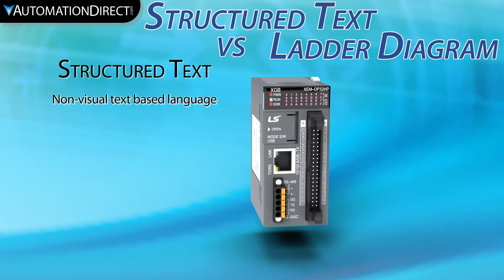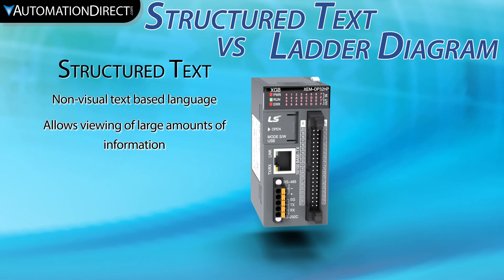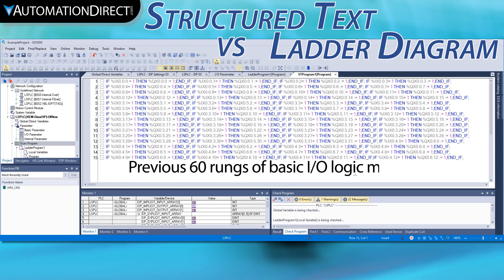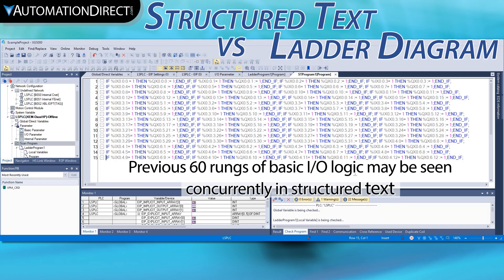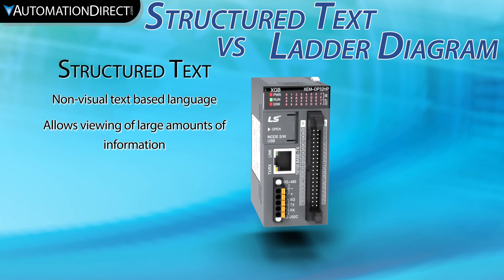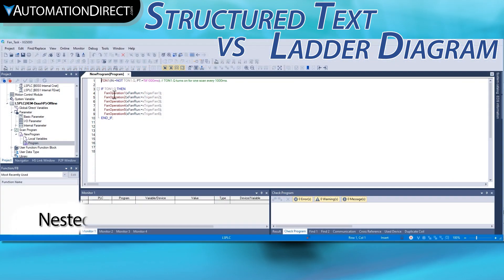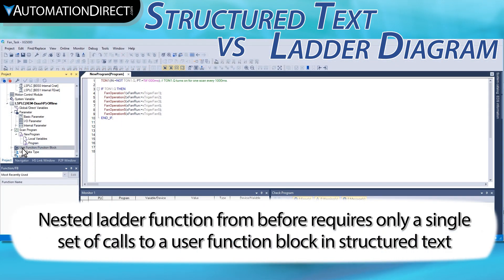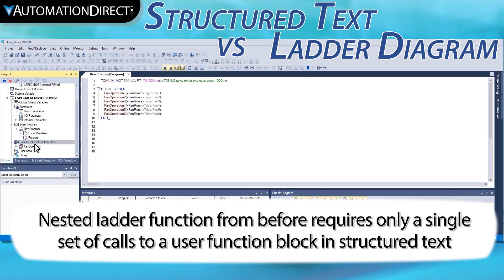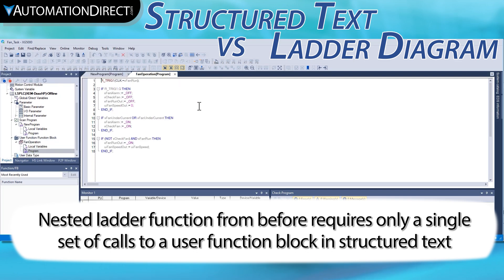Structured Text is text-based, so it is easy to see massive amounts of information on the screen simultaneously. Whether this is 20 functions or 100 variables, performing complex analysis on small programming monitors is easier. Structured Text also allows nested programming for more advanced functions, without the need for multiple ladder views. Normal programming conventions, such as parentheses, can be used as logical separators within a single line of code.